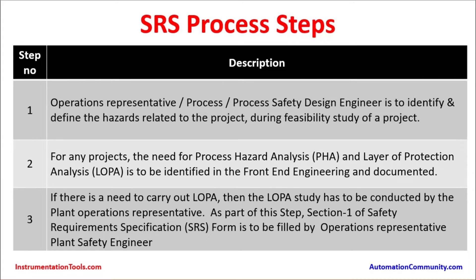In step number one, the operations representative and process safety design engineer are to identify and define hazards related to the project during the feasibility study. The operations team needs to sit together and identify those hazards. In step number two, for any project, the need for process hazard analysis (PHA) and layer of protection analysis (LOPA) is to be identified during front-end engineering and documented.